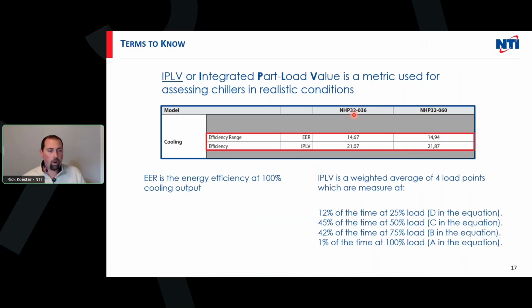This is called IPLV, or integrated part load value, and this is a lot more accurate as far as comparing system to system, or manufacturer to manufacturer. We want to look at our IPLV. Basically, we're looking at the entire season and at the different load points. We're not running at 100% all the time. We actually run at 100% about 1% of the time. For 45%, less than half the time that we run this heat pump, we're going to be at 50% load. So we want to see what the efficiency points are at 25% load, at 50% load, 75 and 100. We take a weighted average of those points, and you're going to see a range of IPLV, which is a much better metric to compare other systems by. It's an apples-to-apples approach, because you don't know what water temp somebody may be using.